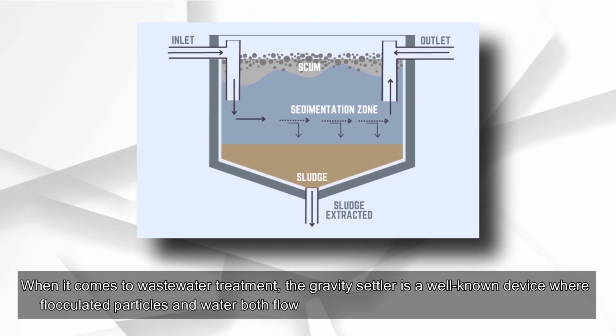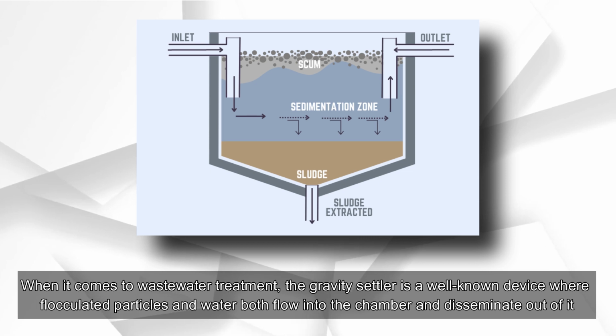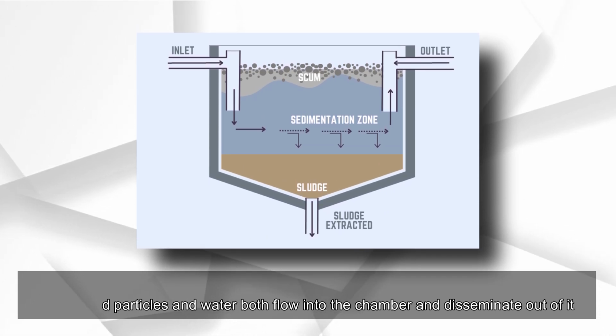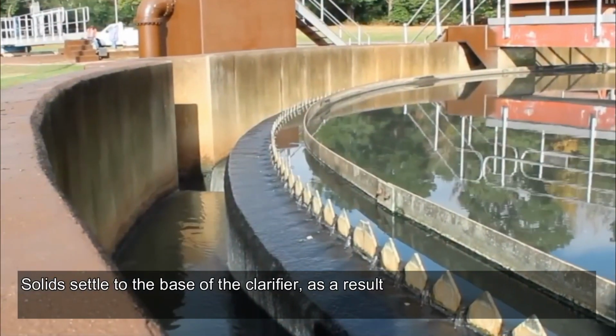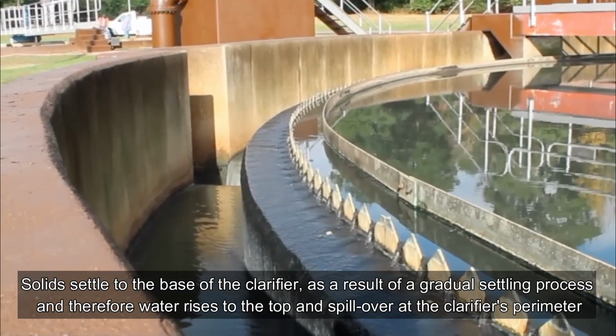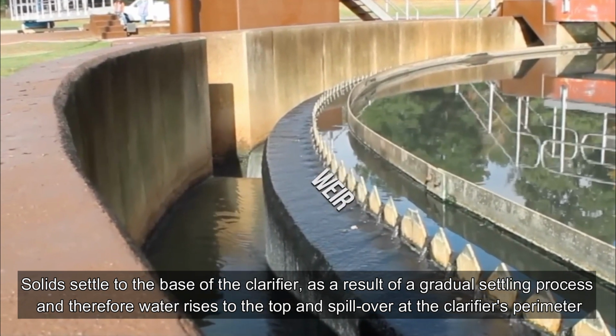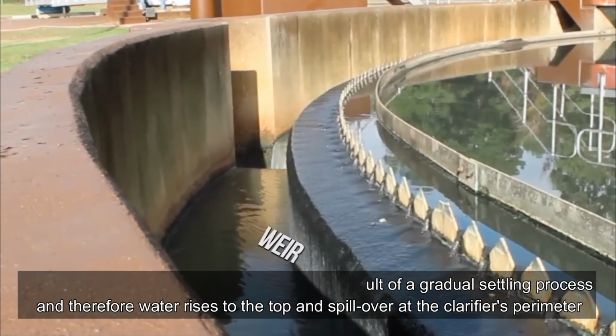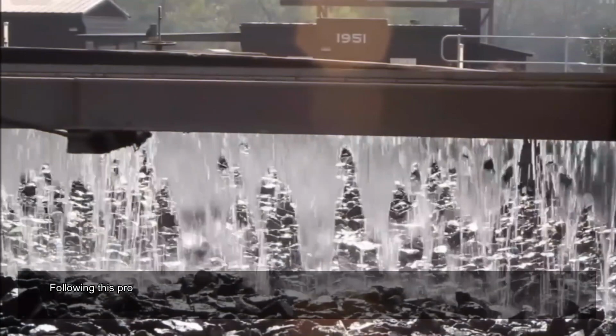Sedimentation. When it comes to wastewater treatment, the gravity settler is a well-known device where flocculated particles and water both flow into the chamber and disseminate out of it. Solids settle to the base of the clarifier as a result of a gradual settling process, and therefore water rises to the top and spills over at the clarifier's perimeter.